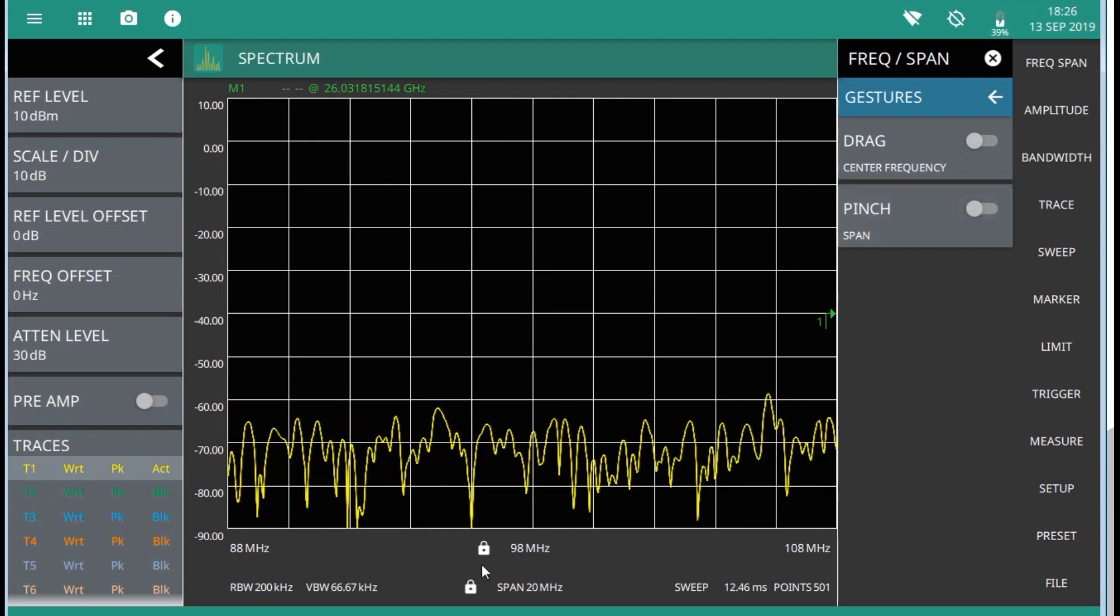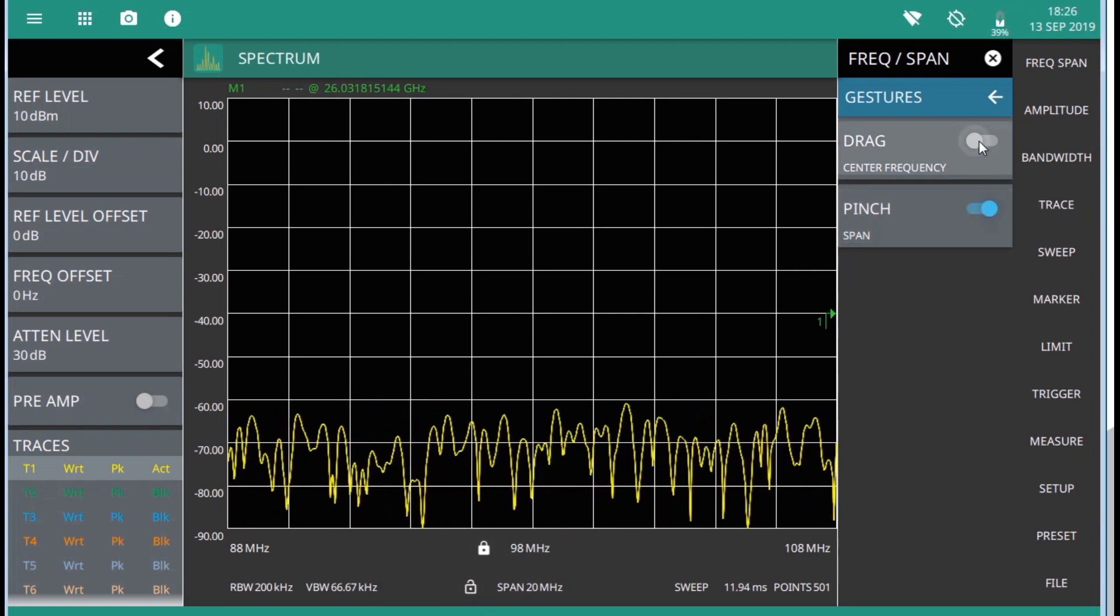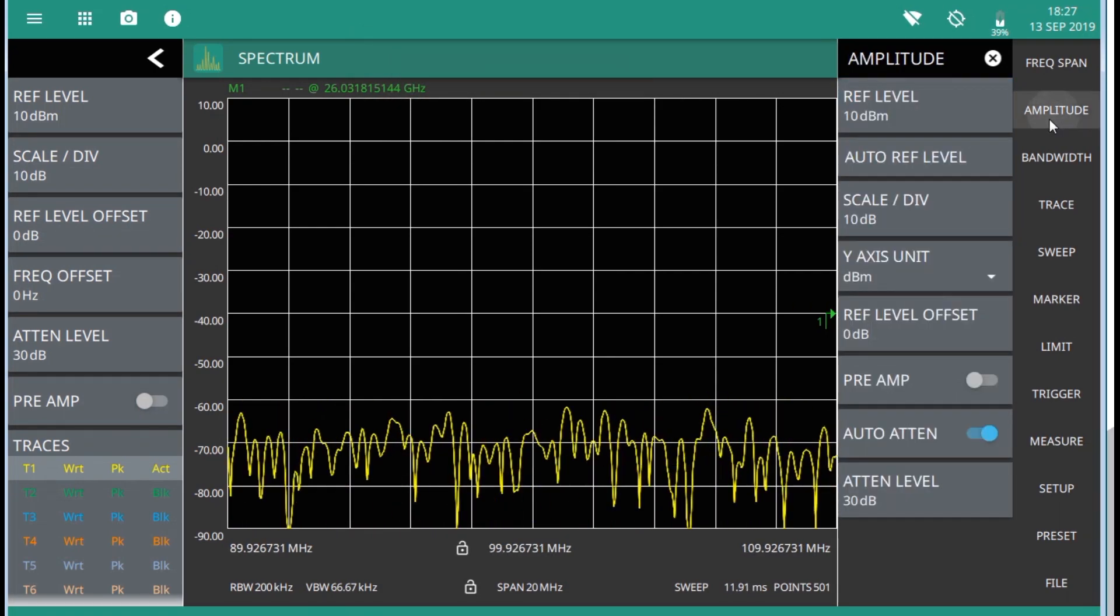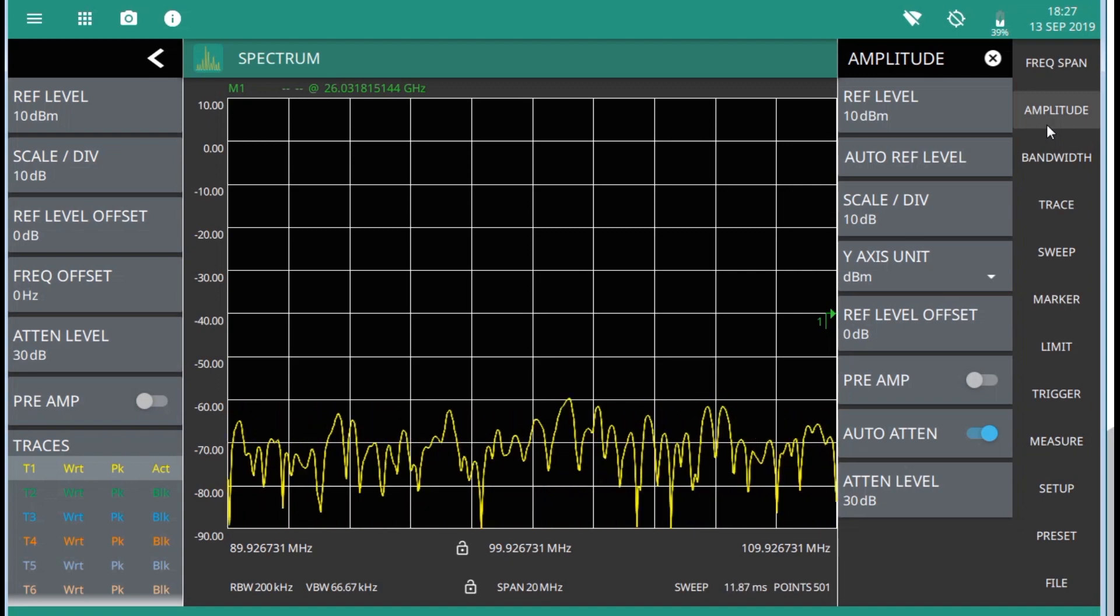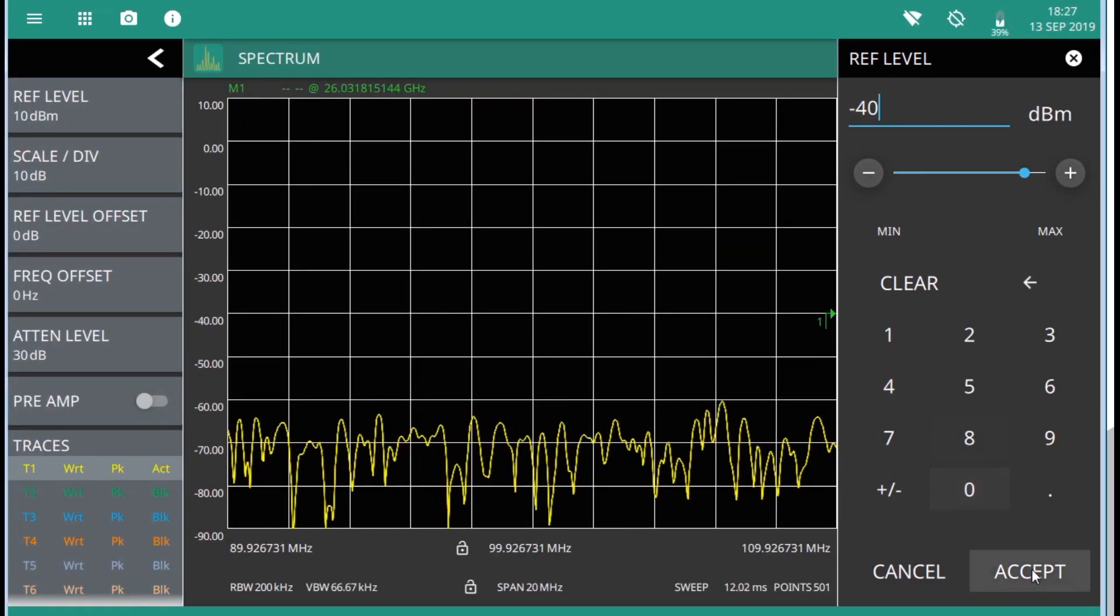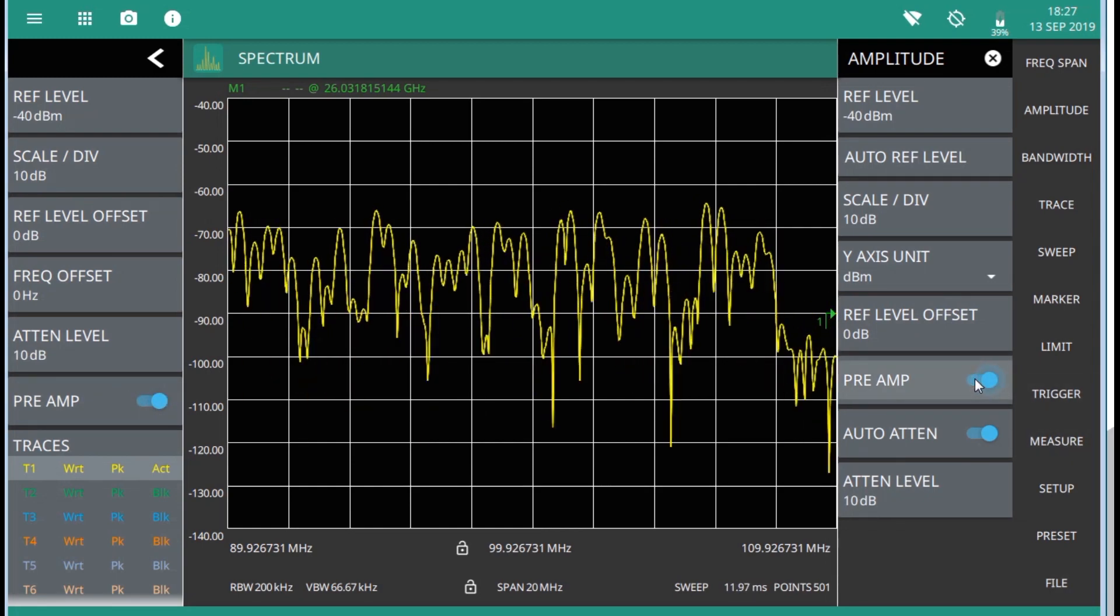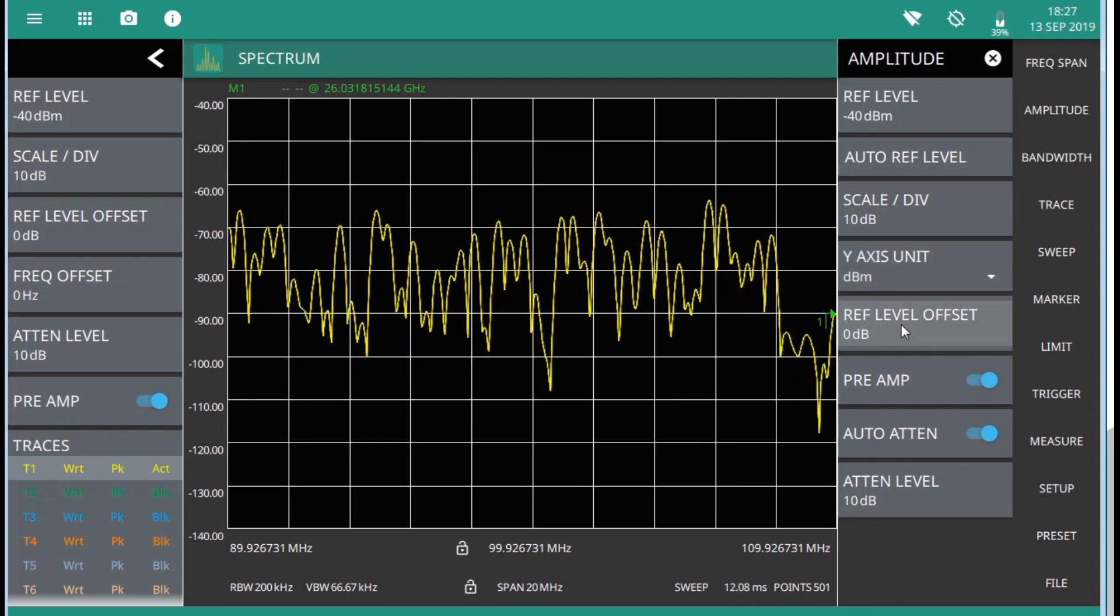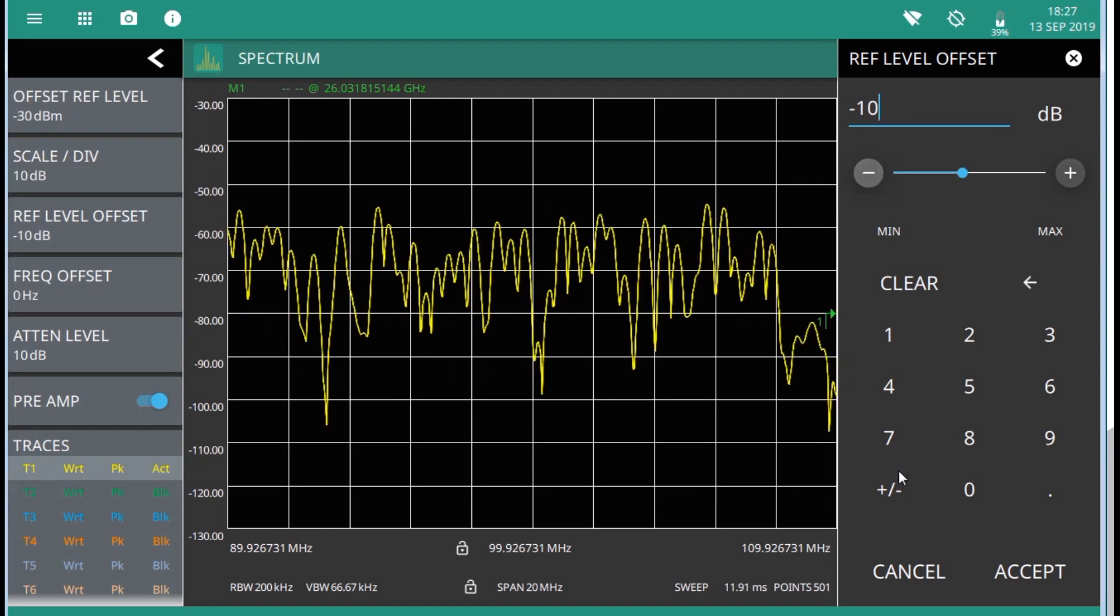Also here you can see gesture settings, for toggle on or off drag and pinch gestures, so locking center frequency and span settings. That can be useful for example when dragging markers, and not to interfere when accidentally changing center frequency or span values. Move on to amplitude menu, I want to get the lower noise floor, and in order to do that, I will decrease the reference level, and use minus 40. Now I am also able to turn on preamp in the RF chain. I can also account for reference level offset, and that could be for external gain or external attenuation.